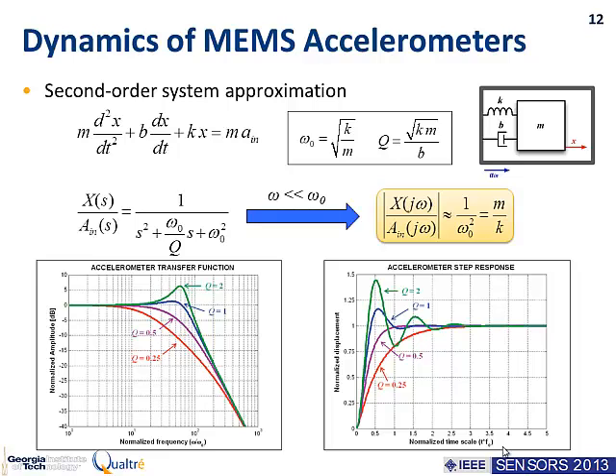Now, this tells us that if my input is much lower than this resonance frequency, then my scale factor is going to be fairly constant in this range. In most situations this is true: resonance frequencies of accelerometers are in the kilohertz to tens of kilohertz range, and usually you want to measure accelerations of no more than a kilohertz or so.